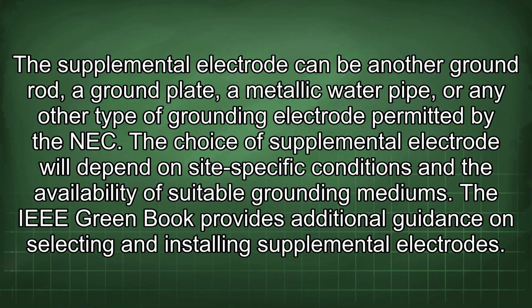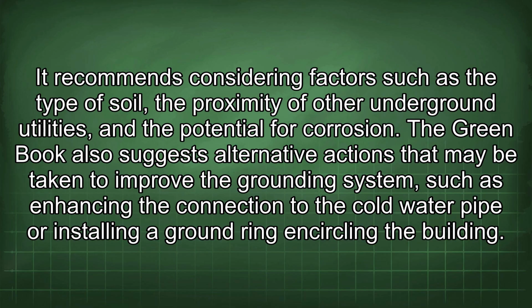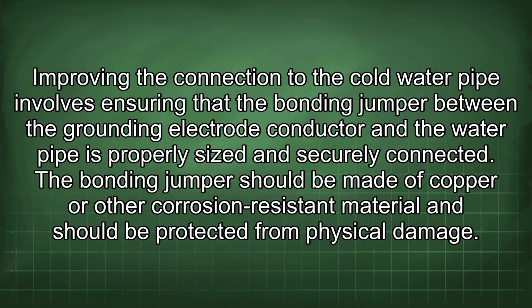The IEEE Green Book provides additional guidance on selecting and installing supplemental electrodes. It recommends considering factors such as the type of soil, the proximity of other underground utilities, and the potential for corrosion. The Green Book also suggests alternative actions that may be taken to improve the grounding system, such as enhancing the connection to the cold water pipe or installing a ground ring encircling the building. Improving the connection to the cold water pipe involves ensuring that the bonding jumper between the grounding electrode conductor and the water pipe is properly sized and securely connected.